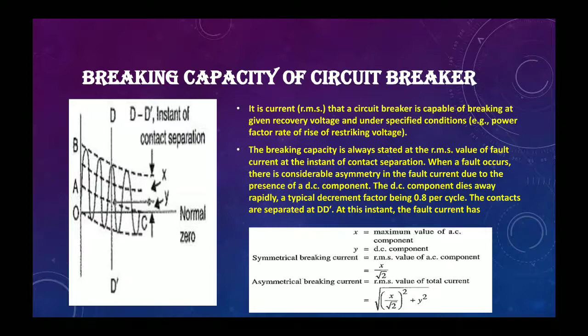Now, it is common practice to express the breaking capacity in MVA, because capacity is always in MVA or kVA. In the case of a circuit breaker, it is rated in MVA, taking into account the rated breaking current and rated service voltage. Thus, if I is the rated breaking current in amperes and V is the rated service line voltage in volts, then for a three-phase circuit, the breaking capacity equals root 3 times V times I times 10 to the power minus 6 MVA. This V is the line voltage. So that is the breaking capacity of a circuit breaker.